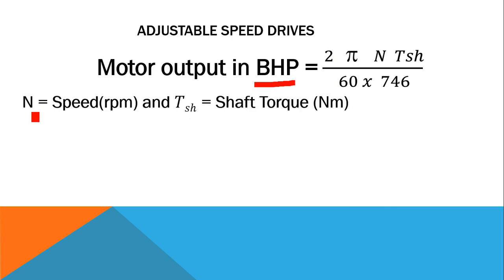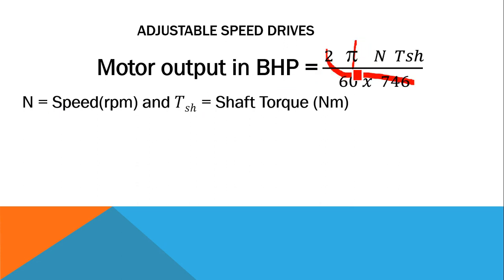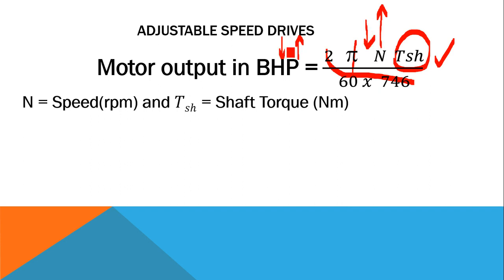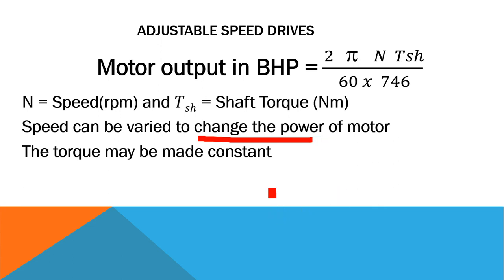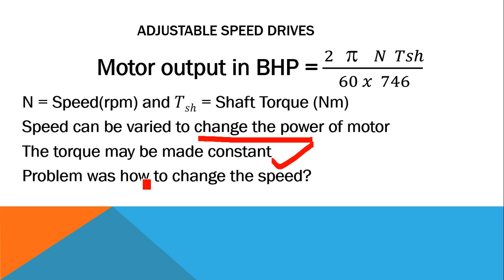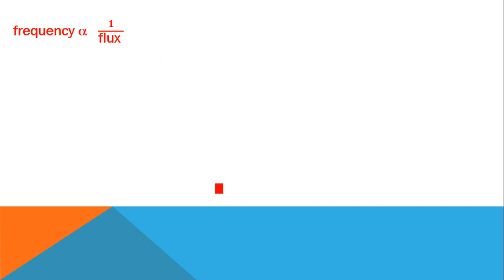In the BHP equation, 2, 60, 746, and π are all constants. So if we control torque to be constant and increase the speed, the BHP will also increase. There is a method where speed can be varied to control the power of the motor. We can control the shaft torque to be constant and vary the speed to change the power of the motor. The synchronous speed equation is N = 120F ÷ P, so the option is to vary the frequency.